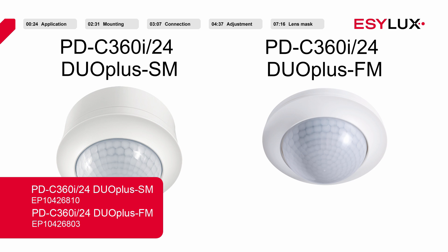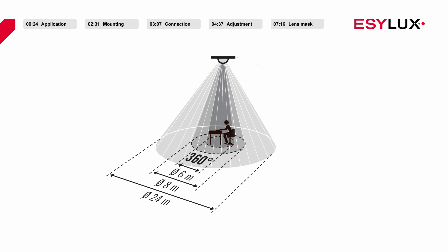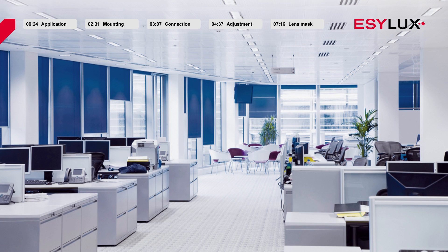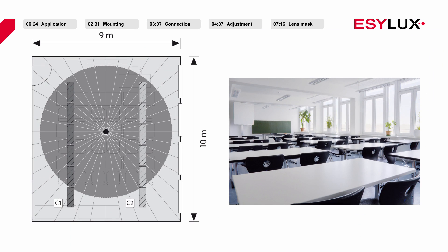Both devices are identical except in terms of how they are installed. They provide a detection range of 24 meters with a 360 degree field of detection. The recommended mounting height is 2.5 to 3 meters. The ESYLUX ceiling mounted presence detectors are ideal for independently controlling two lighting areas, for example in rooms with window areas and internal areas.